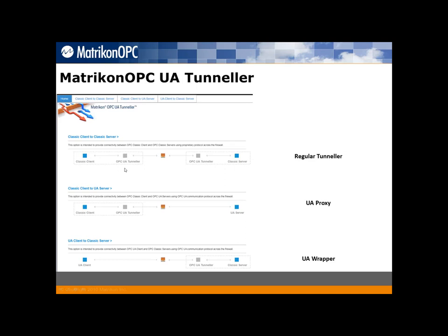We have now included two extra functionalities in the tunneler called UA Proxy and UA Wrapper. These functionalities are designed to integrate OPC classic architectures with OPC UA. For example, the UA Proxy allows us to communicate any OPC UA server with an OPC classic client application. If you have a SCADA using OPC classic, you can communicate with an OPC UA server embedded in a PLC by placing the tunneler together with the SCADA.